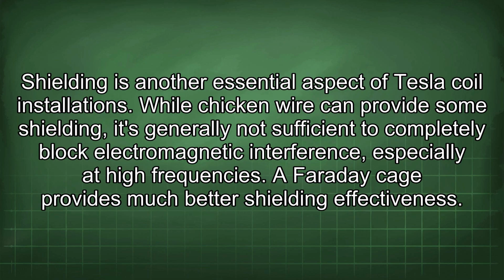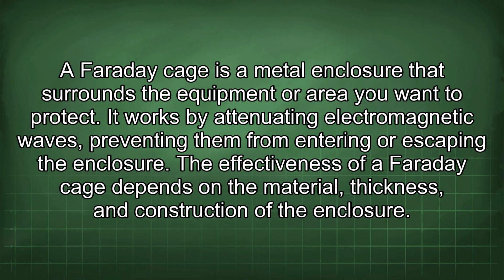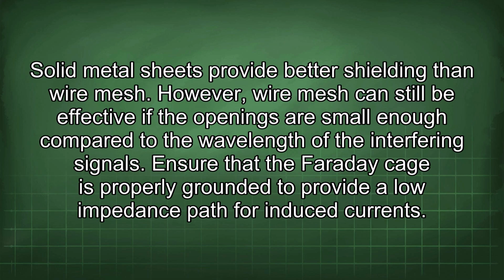Shielding is another essential aspect of Tesla coil installations. While chicken wire can provide some shielding, it's generally not sufficient to completely block electromagnetic interference, especially at high frequencies. A Faraday cage provides much better shielding effectiveness. A Faraday cage is a metal enclosure that surrounds the equipment or area you want to protect. It works by attenuating electromagnetic waves, preventing them from entering or escaping the enclosure. The effectiveness of a Faraday cage depends on the material, thickness, and construction of the enclosure. Solid metal sheets provide better shielding than wire mesh. However, wire mesh can still be effective if the openings are small enough compared to the wavelength of the interfering signals.